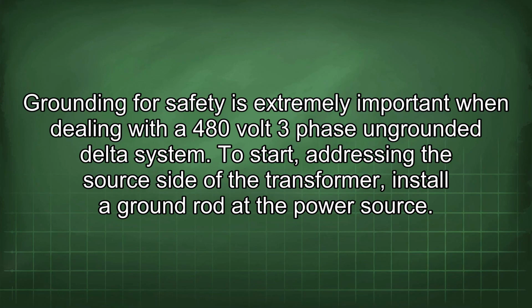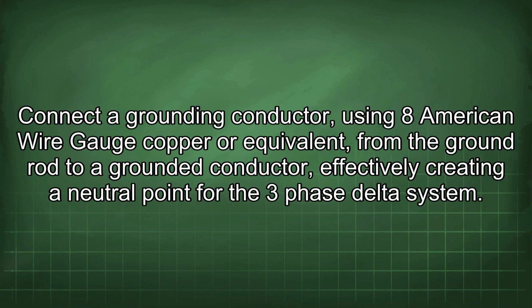Grounding for safety is extremely important when dealing with a 480-volt three-phase ungrounded delta system. To start addressing the source side of the transformer, install a ground rod at the power source. Connect a grounding conductor using 8 American wire gauge copper or equivalent from the ground rod to a grounded conductor, effectively creating a neutral point for the three-phase delta system.